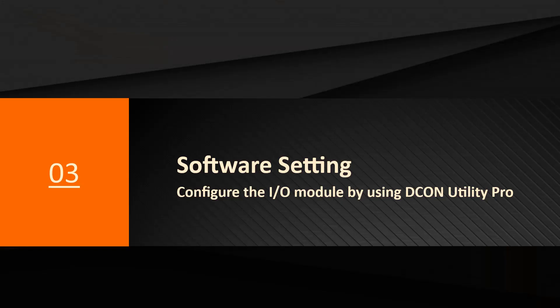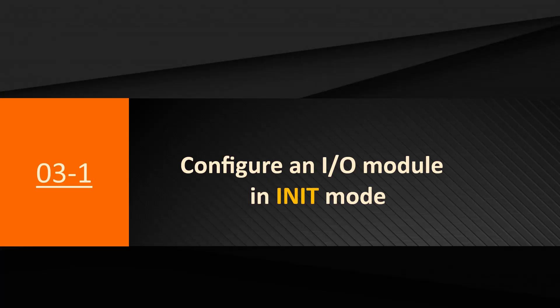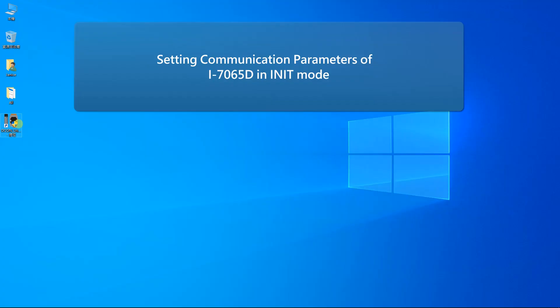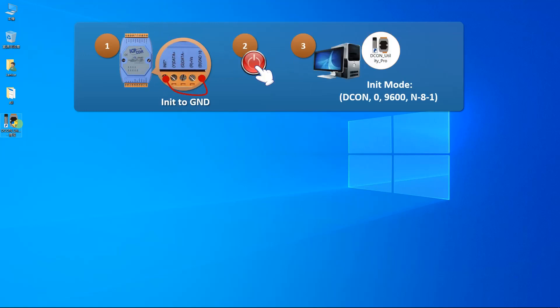Next we will introduce how to use the DCON Utility Pro to configure modules. If the module's current protocol setting is DCON, the communication parameters can only be changed in init mode. The I7000 series only supports the DCON protocol, so we need to change communication parameters in init mode. Set the init wiring, power up the module, and execute DCON Utility Pro on the PC.